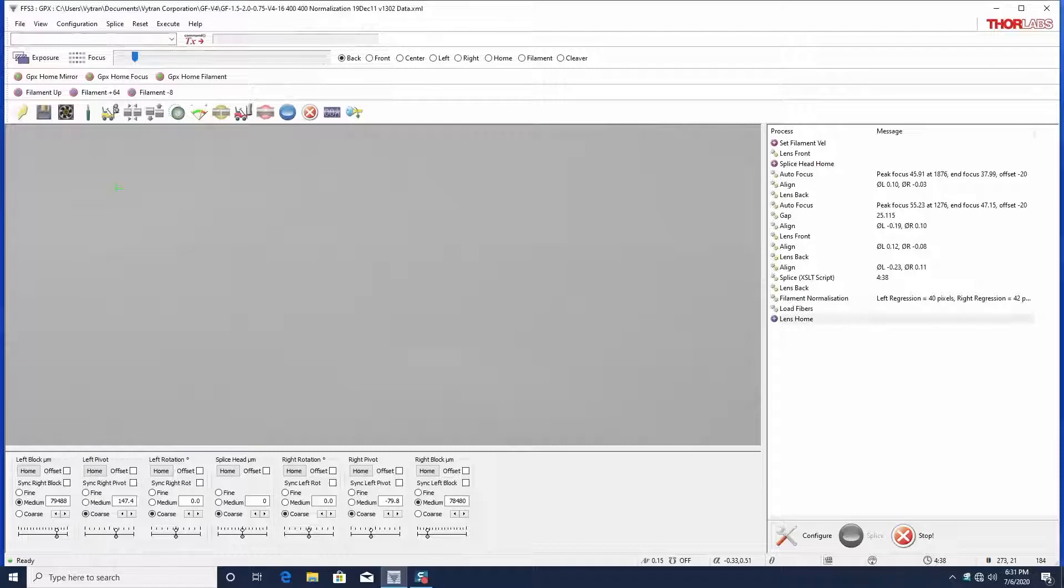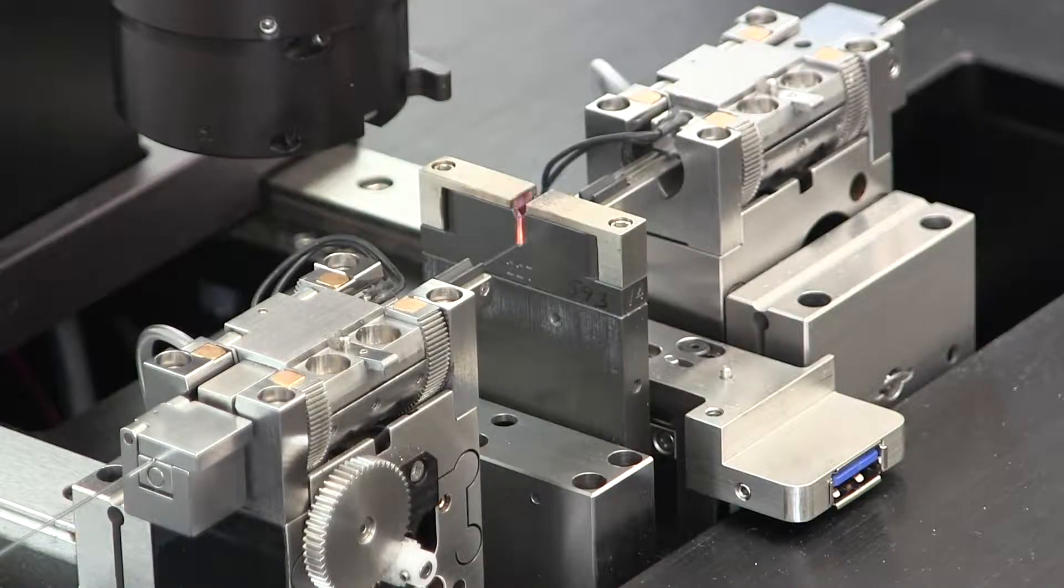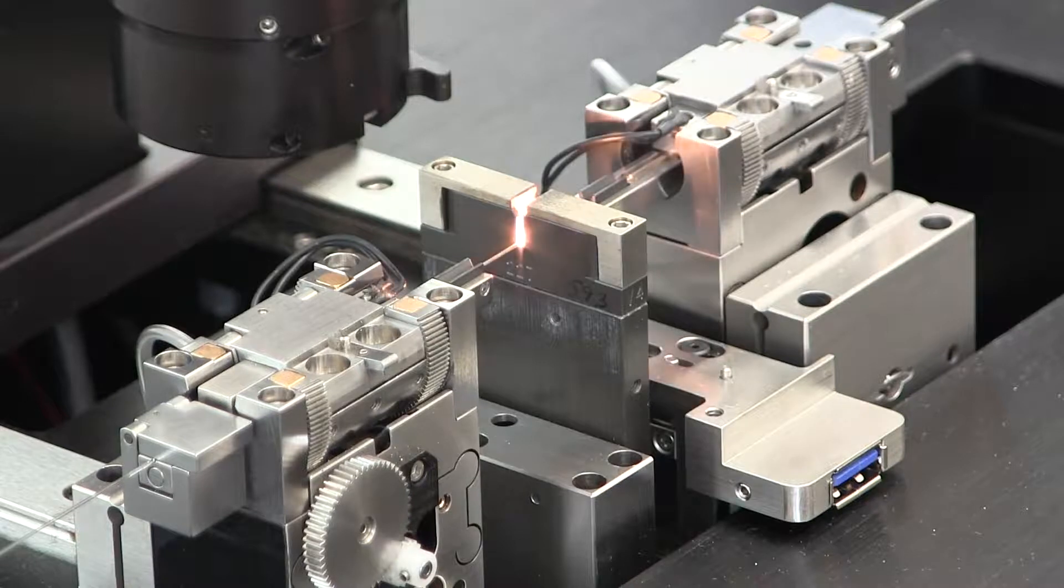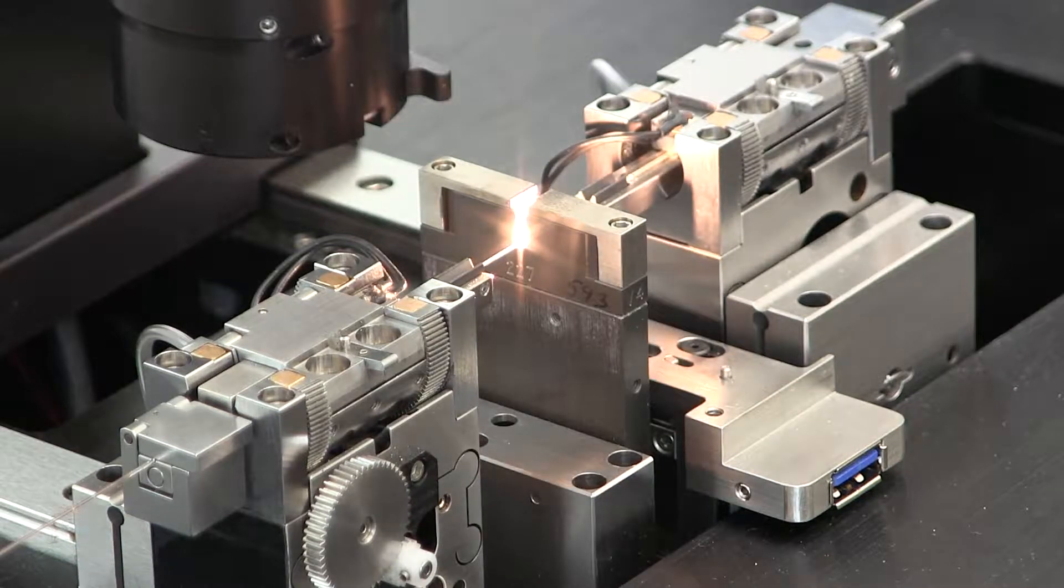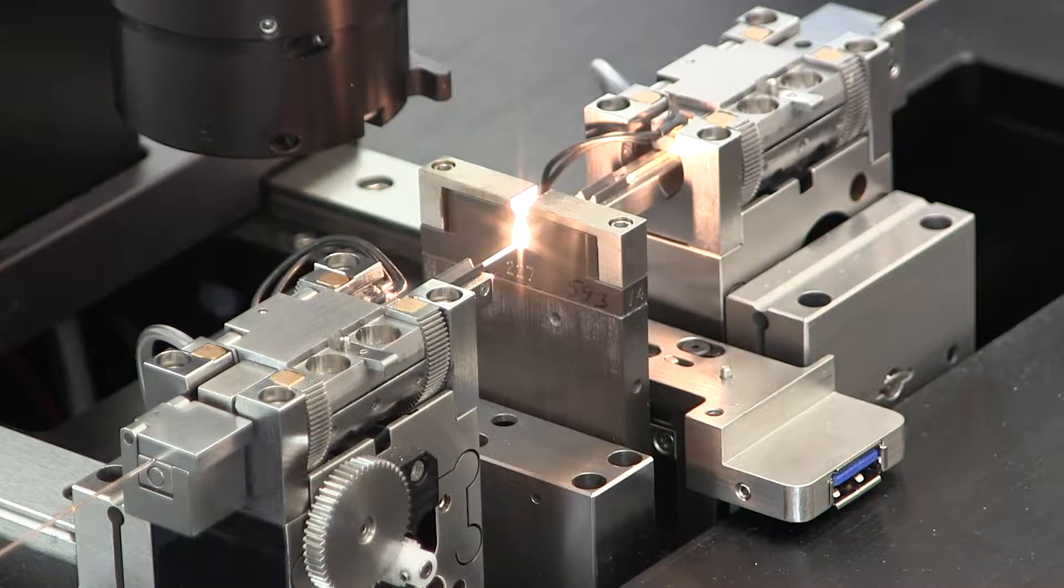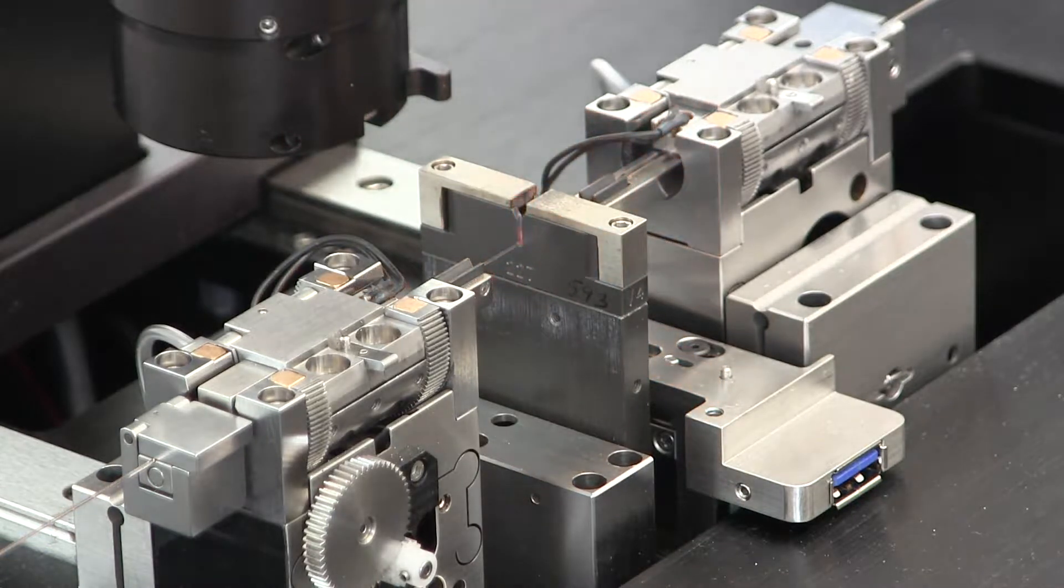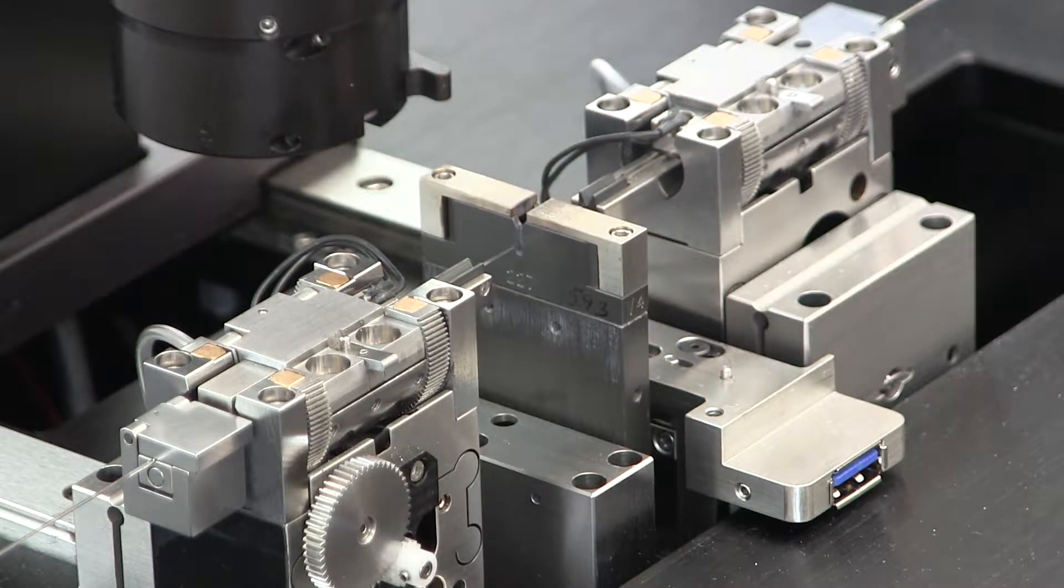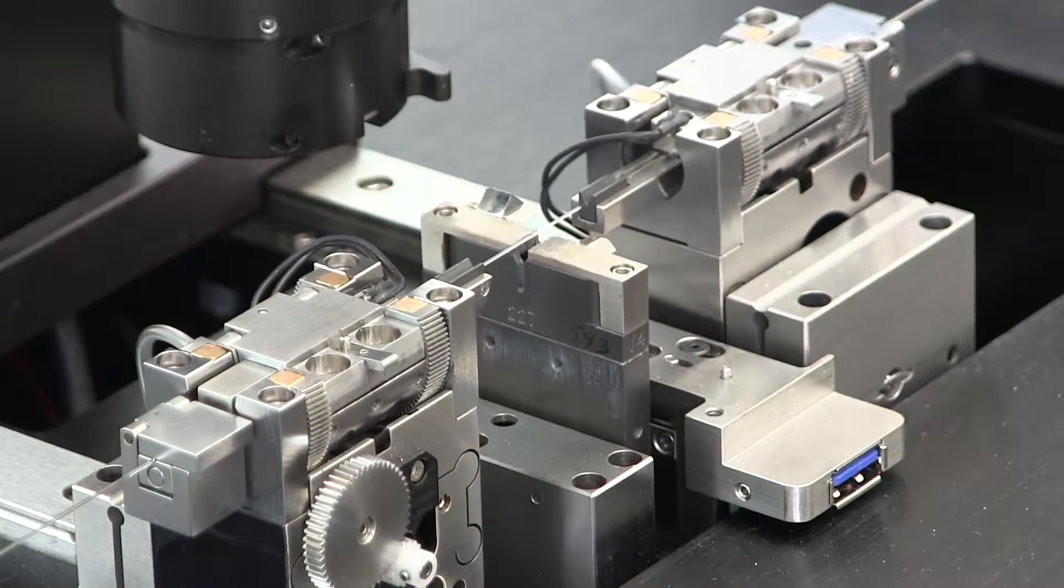It will not be necessary to burn in this filament again. As the filament reaches the end of its useful life, the thermal power delivered may become unstable. When this happens, splice performance may degrade, or the normalization may not converge. At that time, contact us about refurbishing your filament.